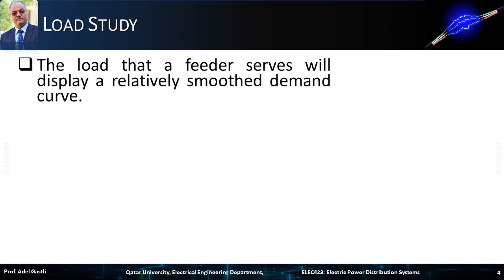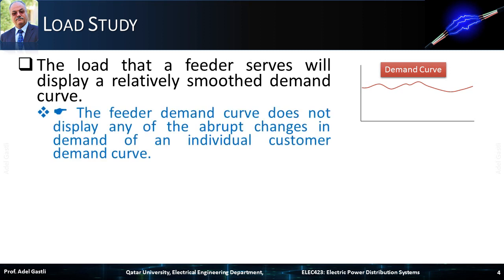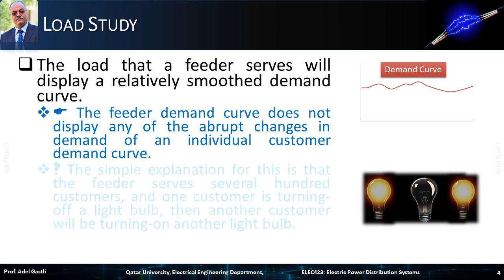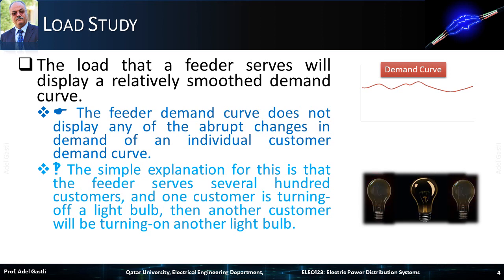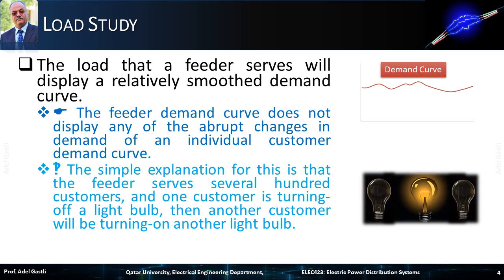It is worth noting that in most cases, the load that the distribution feeder serves will usually display a relatively smoothed demand curve. So the feeder demand curve usually does not display any of the abrupt changes in demand of an individual customer's demand curve. The simple explanation for this is that the feeder serves several hundred customers, and when one customer is turning off a light bulb, then another customer may be turning on another light bulb. Therefore, the main distribution feeder will not experience any significant change in the load.